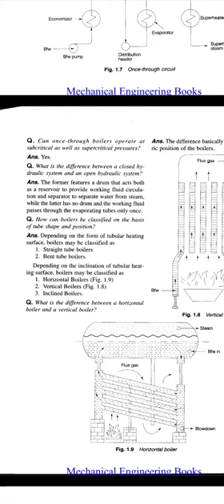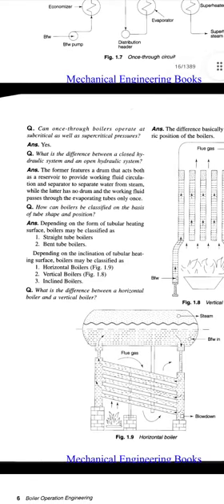Can once-through boilers operate at subcritical as well as supercritical pressure? Yes. What is the difference between a closed hydraulic system and an open hydraulic system? The former features a drum that acts both as a reservoir to provide working fluid circulation and to separate water from steam, while the latter has no drum and the working fluid passes through the evaporating tubes only once.